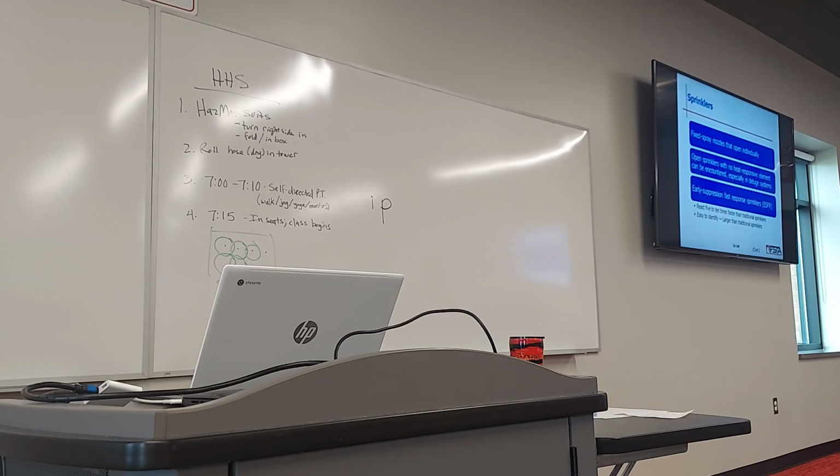But the majority of fires that have sprinkler systems in the room are controlled by one sprinkler head. 95%, one sprinkler head. 98% are controlled by two sprinkler heads. So very rarely do we get a fire that sets off more than two sprinkler heads.